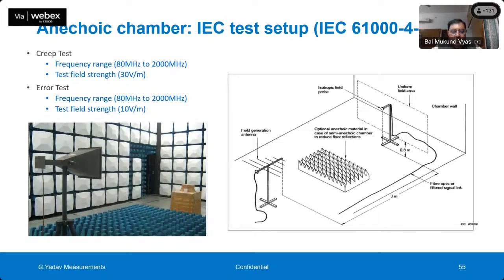So this is a big chamber, a very expensive test, and only 1 meter can be tested at a time, because if you keep 2 meters, then there can be influence of 1 meter on the other meter. So this is a very expensive test, and it sometimes takes more than 10 hours to complete the testing of 1 meter.